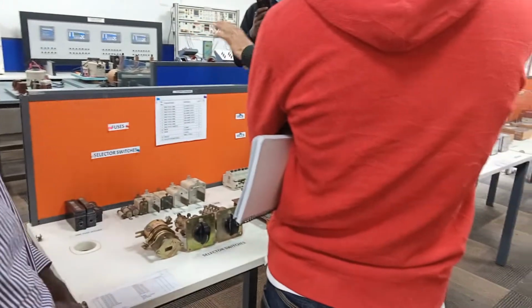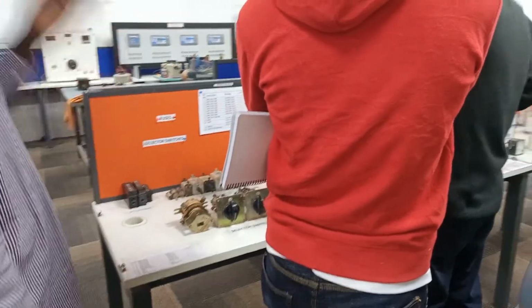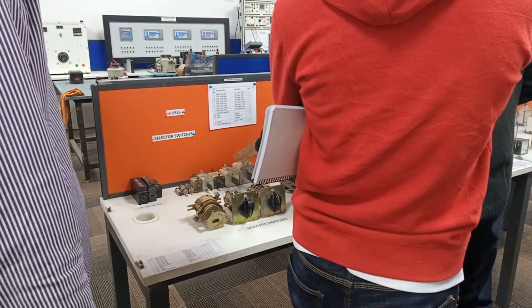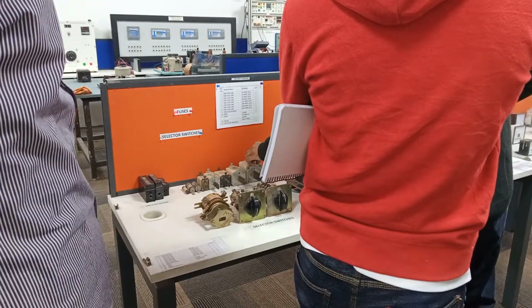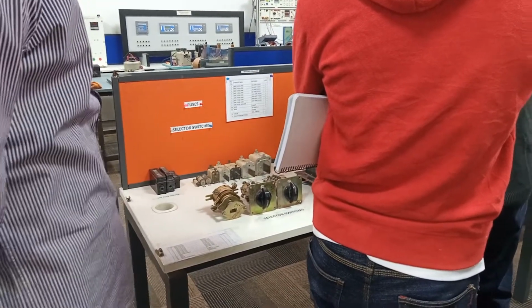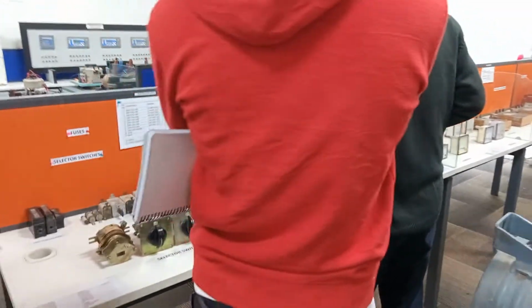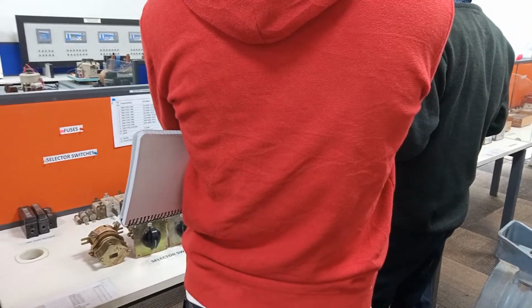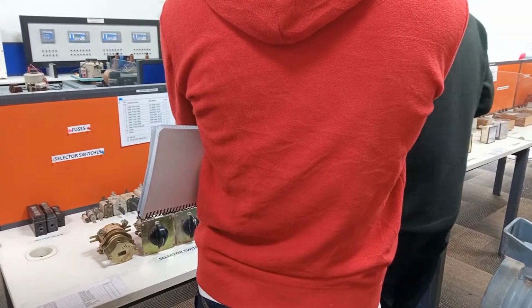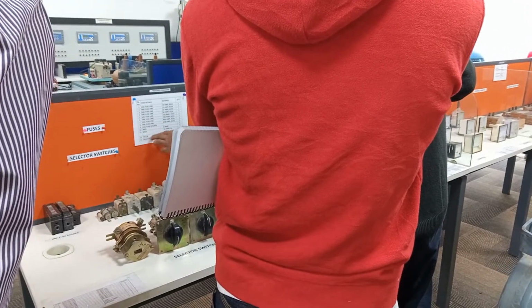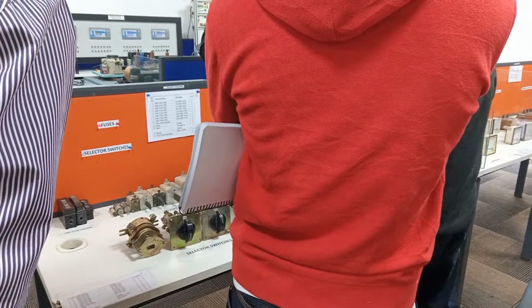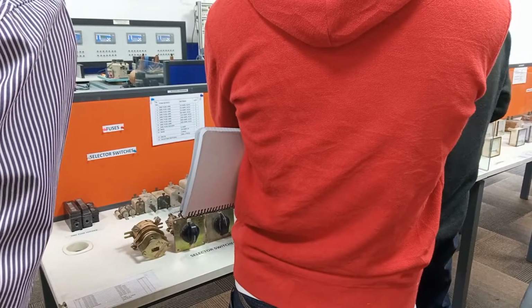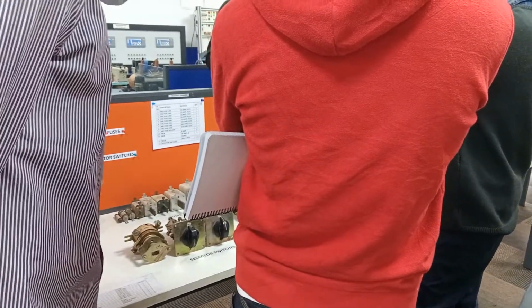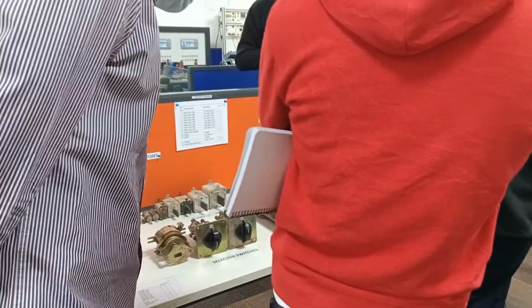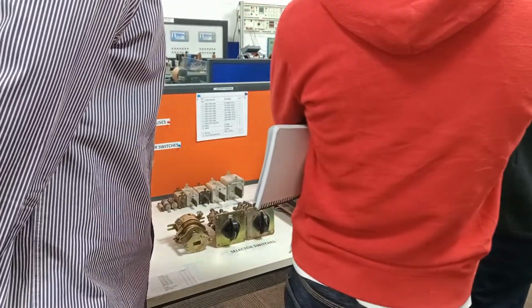Yes. I hope it is very clear what the rating is and what the uses of these fuses are. And nowadays it is not at all fuses. In special cases, certain contactors and others, nowadays it is this MCB or MCCB. What is MCCB? Molded case circuit breaker. So it is slightly higher. With MCB there are certain limits. If you see the limits here, they are just mentioned for visibility at present. Once we exceed this 100 amps, it would be MCCB.